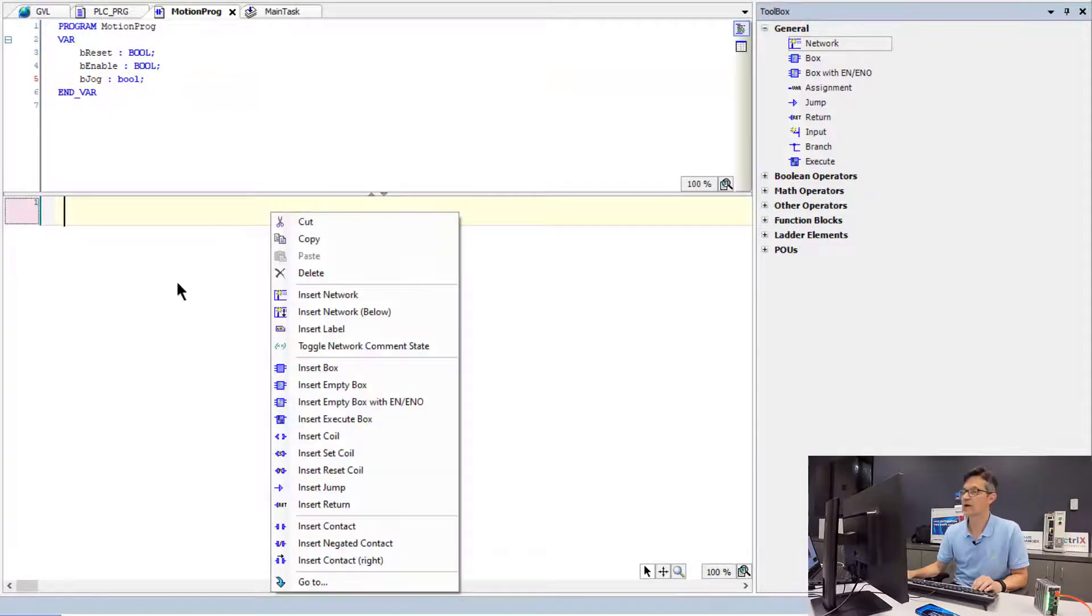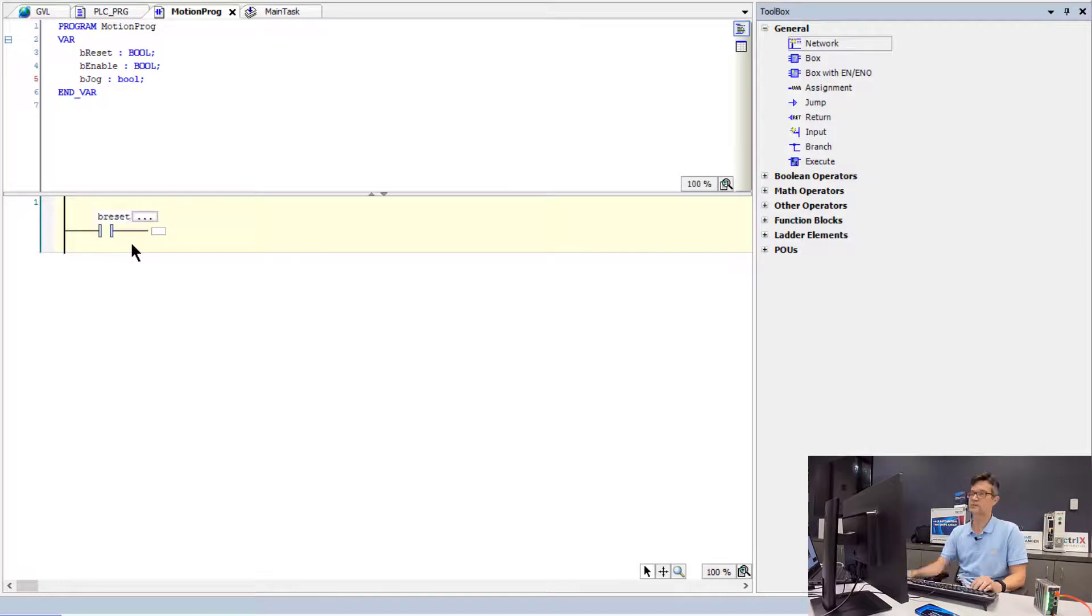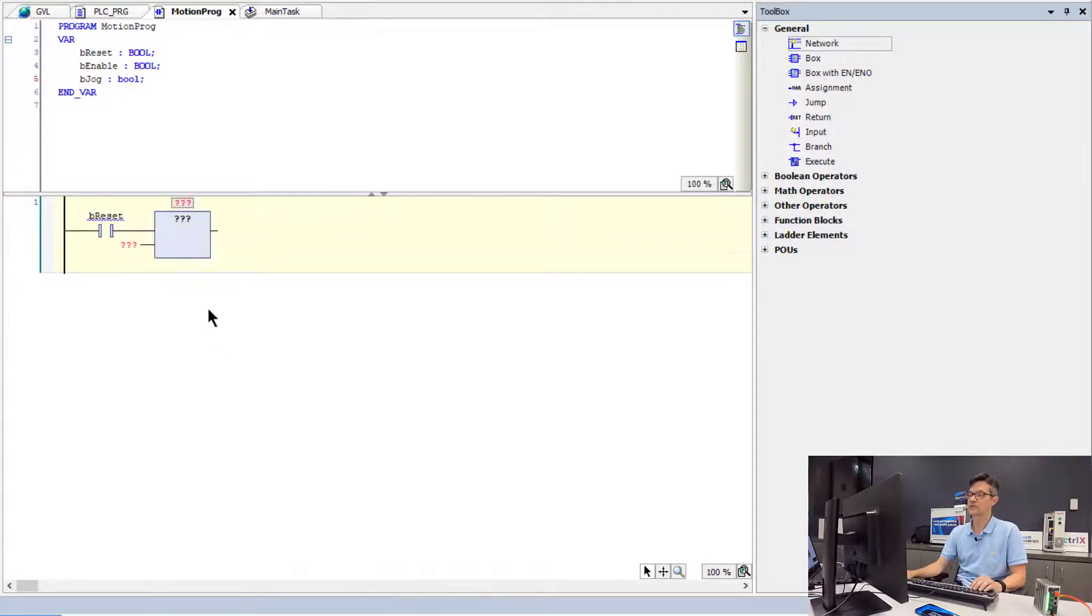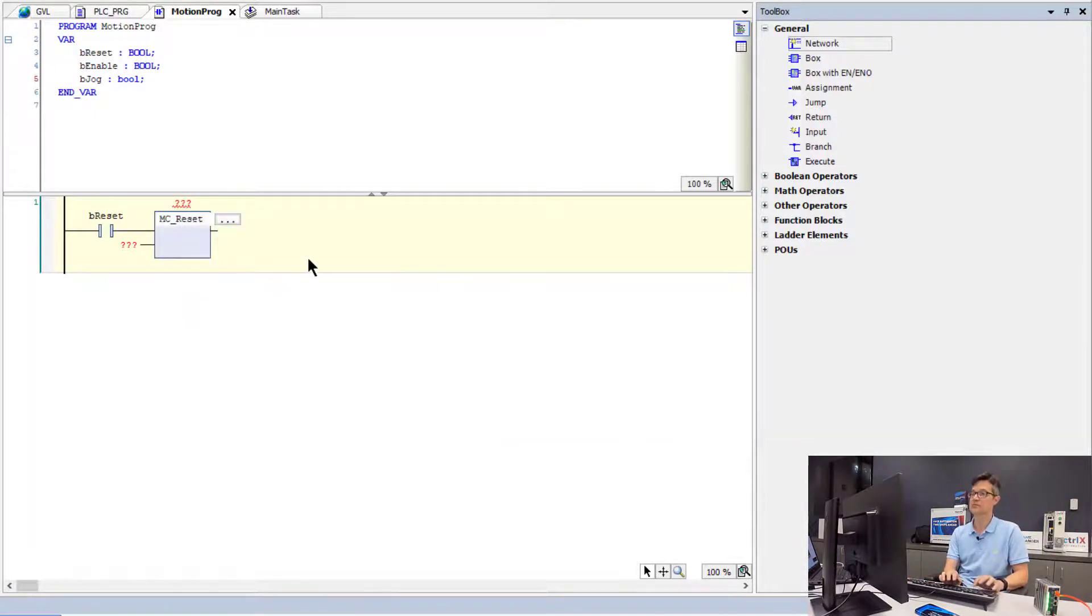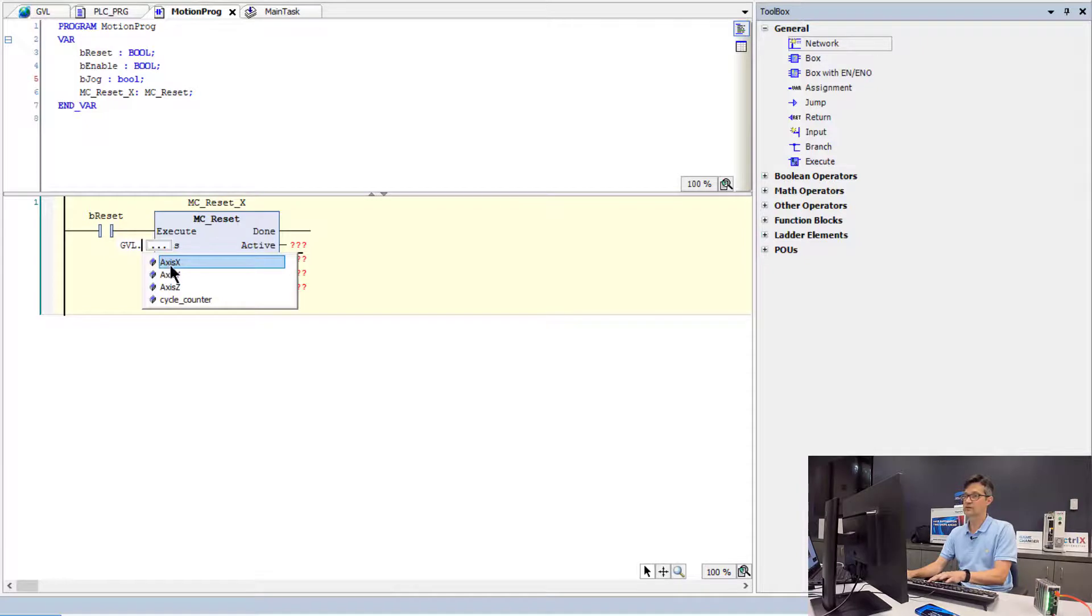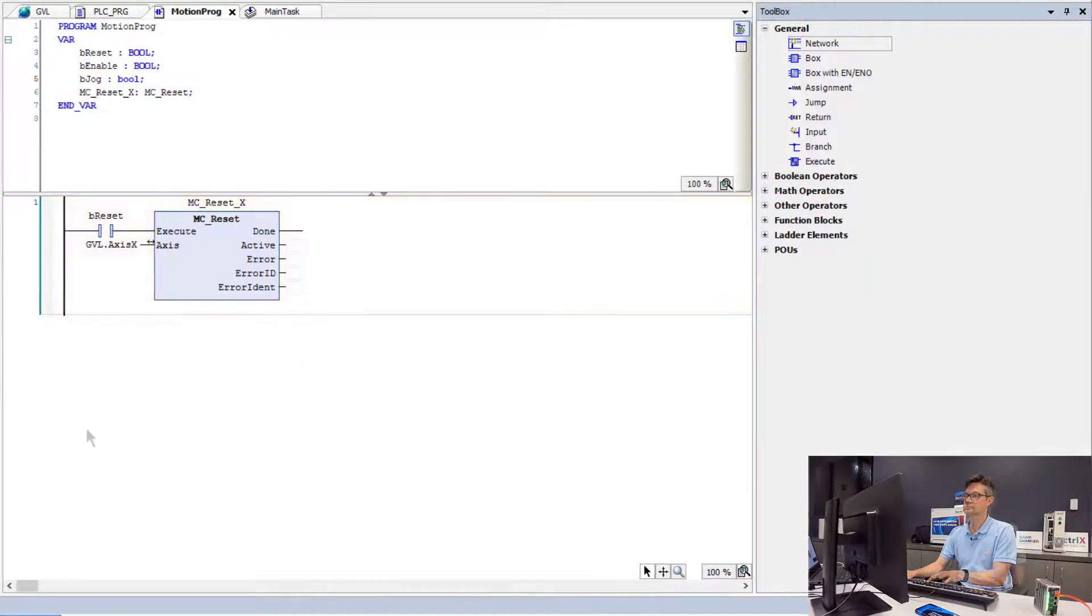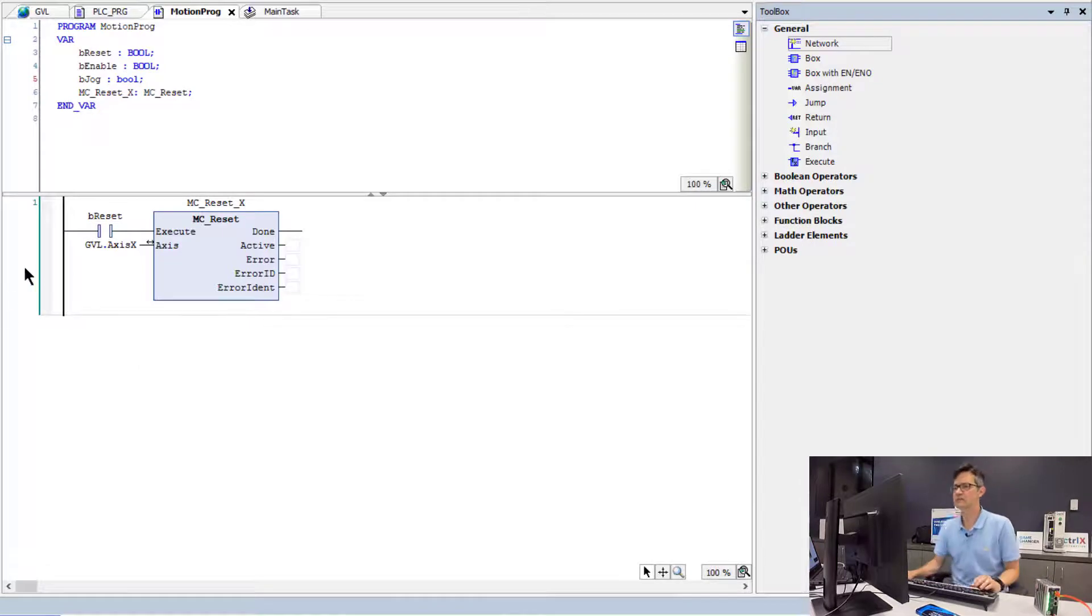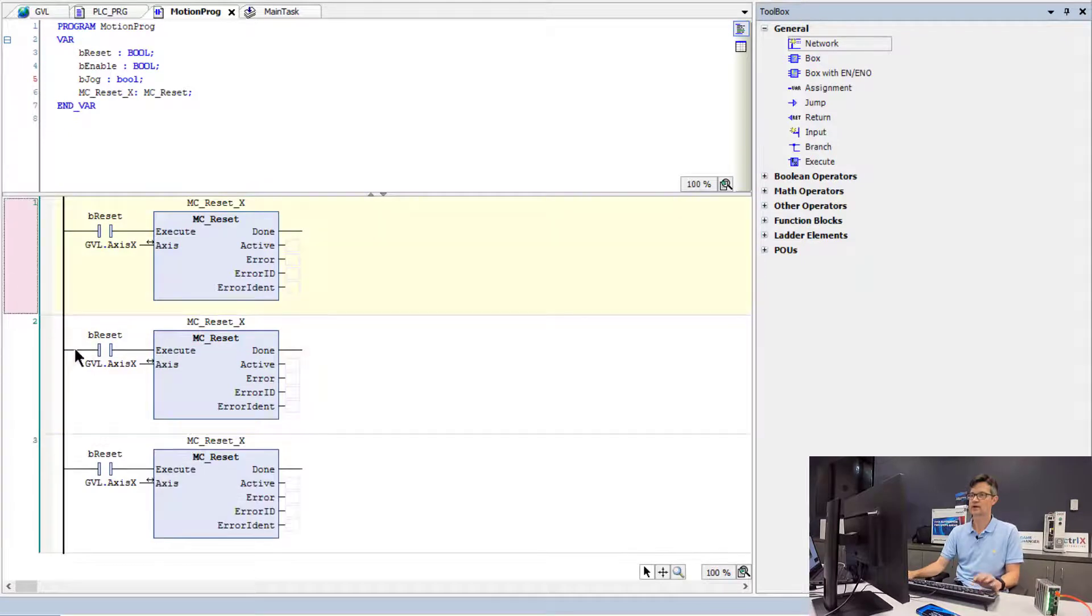Now we will add the functions, the corresponding functions for these commands. So for reset, we will add a box and we will use the MC Reset function block. We will now have to declare each instance of the function block. If I add to Axis X, we will need to remove these question mark fields on the output of each block. So we will now make three copies, we will make two copies of this function block for the X, for the Y and the Z.